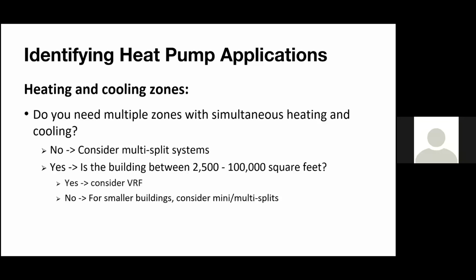Do you need simultaneous heating and cooling, or do you have an application where maybe you have classrooms, right? And maybe you're at more of a lower budget. Hey, these students don't really need cooling; they just kind of need heating at this point. We can do heating or cooling at one time. Why don't we just keep it a heat pump system, and we'll do a schedule based on the seasons, basically. So shoulder season hits. If April 1st hits, we're going to go to cooling mode, and then October 1st hits, we're going to heating mode, basically. So not everything needs simultaneous heating and cooling, but most applications with a lot of zoning do.